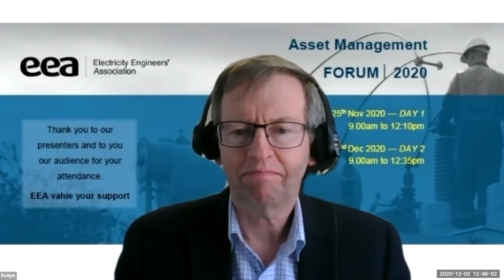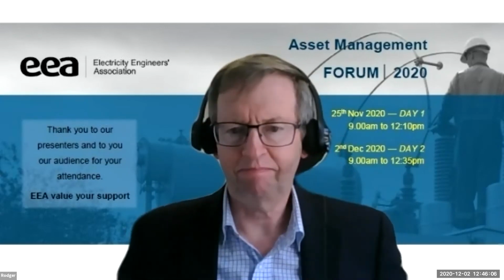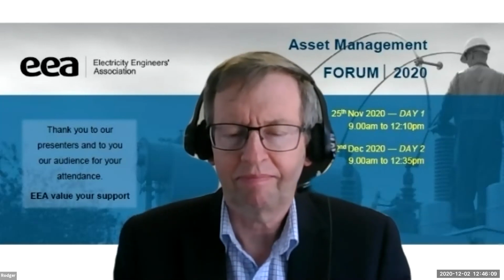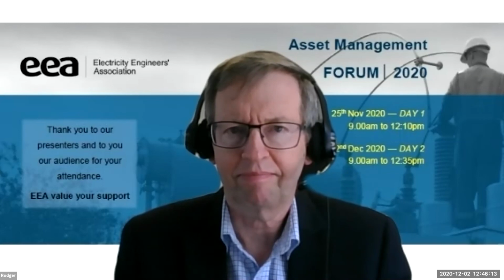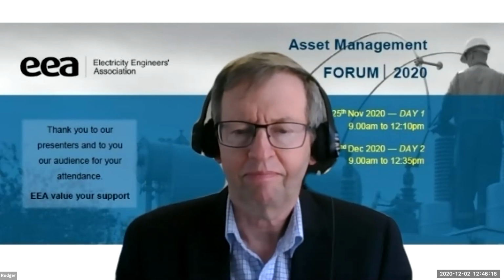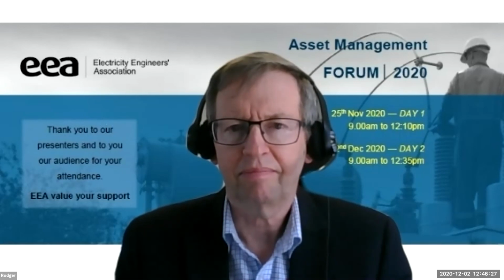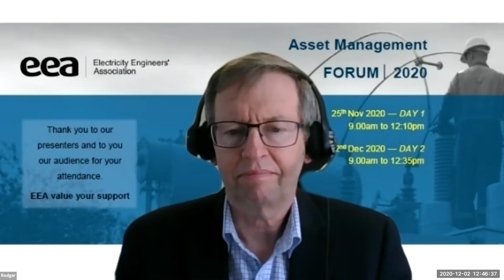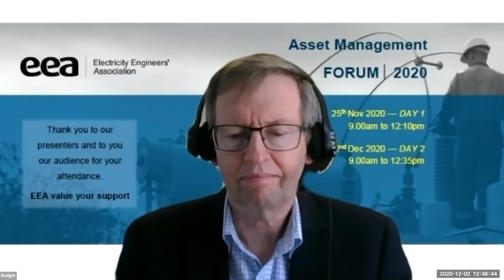I think I touched on it briefly. We have been doing measurements, and traditionally 20 years ago, with the air conditioner revolution in Western Australia, our peaks were uncontrollably increasing because everyone could afford reverse cycle air conditioners with direct on-line type compressor motors, and our peak load was very inductive, around 0.95, 0.9 power factor, with the VARs being sourced from our generation.